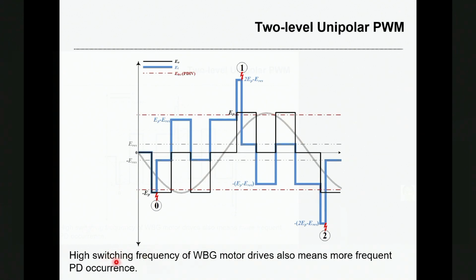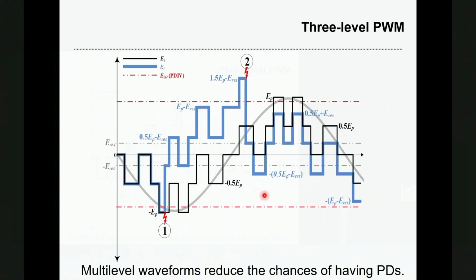And also the high switching frequency of wide-bandgap motor drives also means more frequent PD occurrence, because you have more pulses within a certain time under high switching frequencies. So you can also use that to analyze a three-level PWM. Generally speaking, you will get fewer PD events for a multi-level waveform, because the dV/dt, the delta V, is smaller.